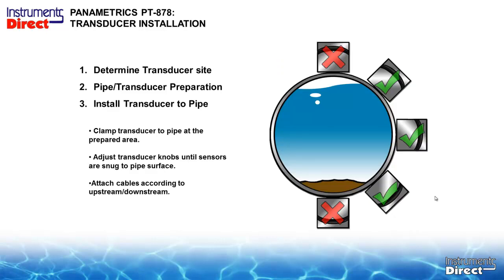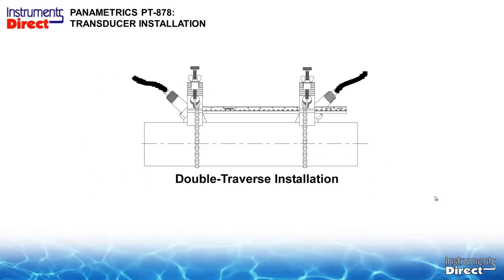As far as location on the pipe, vertical, horizontal doesn't make any difference, but note on the horizontal, at the top of the pipe at 12 o'clock you can have aeration, and at 6 o'clock, you can have some buildup and some debris. So anything on the side of the pipe, anything from 1 to 4 o'clock is probably a better location. So here's a picture of the traditional dual traverse where there's both sensors on the same side of the pipe. Again, this is a bird's eye view, so it's not at 12 o'clock, say it's 3 or 9 o'clock.